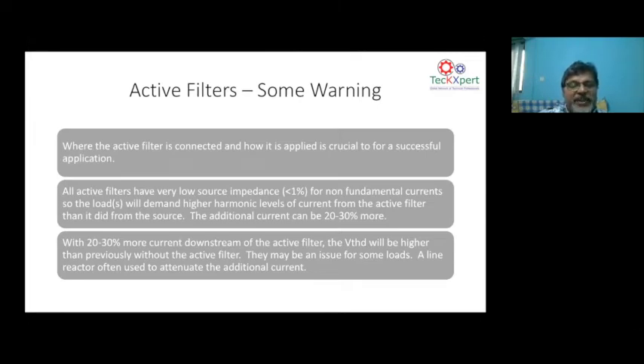And active filters have a very low source impedance. This is a very important point, because sometimes people put an active harmonic filter in a network, and if your variable frequency drives don't have any line reactors, then what happens? Your active harmonic filter, being a low source impedance, will inject more harmonic currents. So when you select an active harmonic filter, you need to make sure that the drives have proper line reactors. Otherwise, an additional current of 20 to 30% more will be demanded from the active harmonic filter. And sometimes the active harmonic filter can get overloaded because of this reason. So 20 to 30% more current downstream. Okay, go to the next.